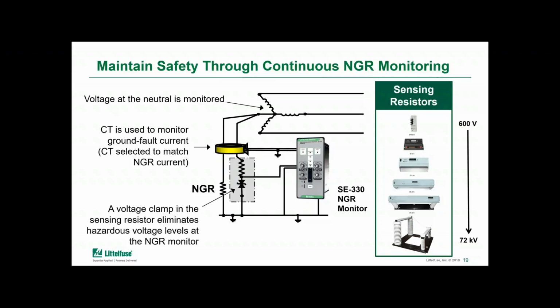This control shown here, which is a continuous NGR monitor, is a little bit of a misnomer, because an NGR monitoring device will verify the complete neutral to ground connection. So it's not strictly the NGR, but also the connection from neutral to ground, including the NGR. In the example here, there is a sensing resistor device to provide a connection to the system, and it allows a small current to flow from the relay that is measuring the neutral to ground resistance. Since that's part of the monitoring logic, it also facilitates voltage monitoring of the neutral as well.